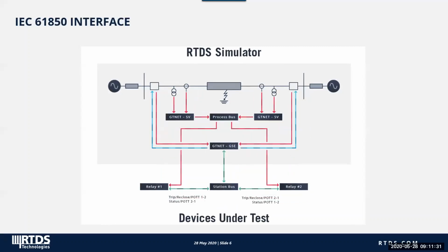Now, if the device under test supports IEC 61850 and the focus is to use it for the specific application, then the IEC 61850 interface may be applied. As shown in this slide, we have the same power system simulated in RTDS. For data transmission, instead of using the conventional I/O cards, the network communication card, the GTNET or GTNET X2, is used. The GTNET card is the older generation and the GTNET X2 is the current generation. From here, I will use the term GTNET to refer to both GTNET and GTNET X2, unless the differences between the two need to be addressed.